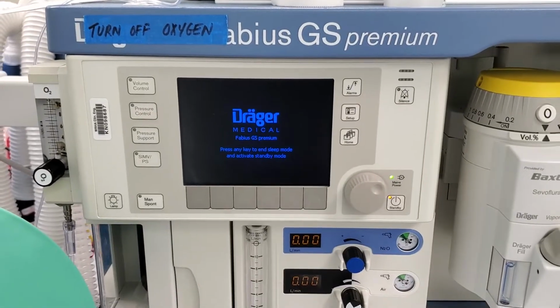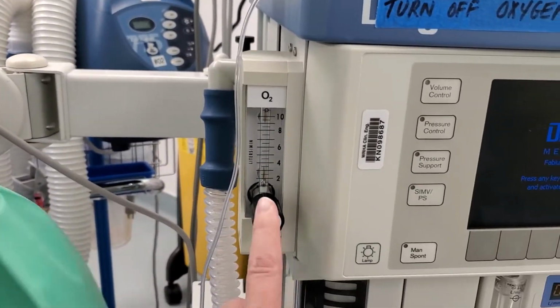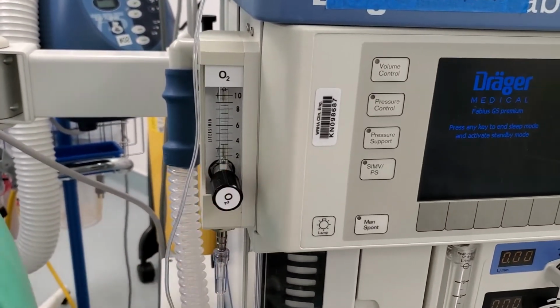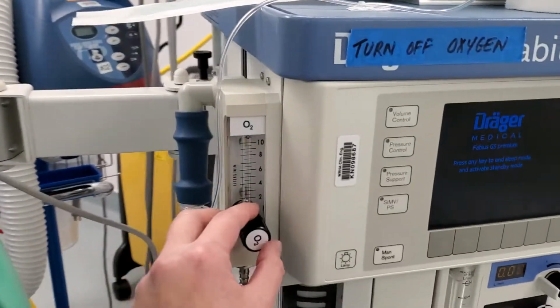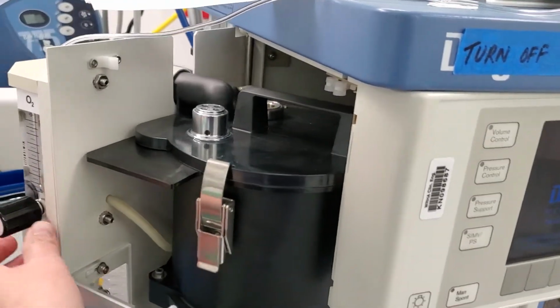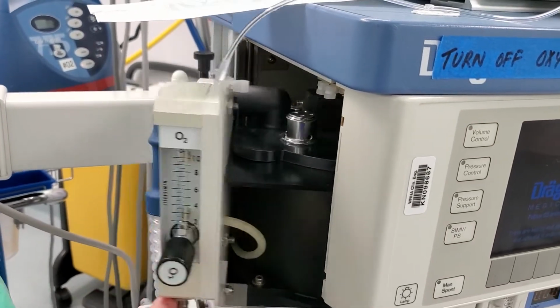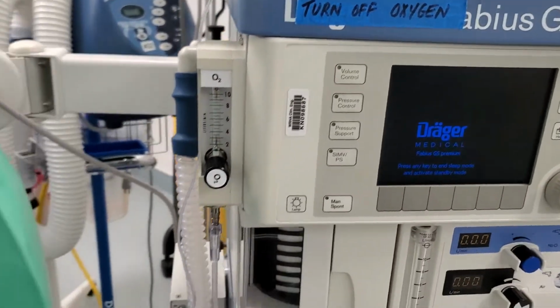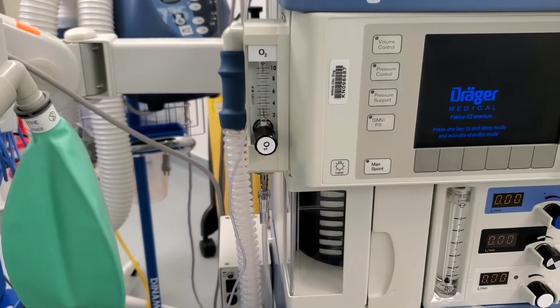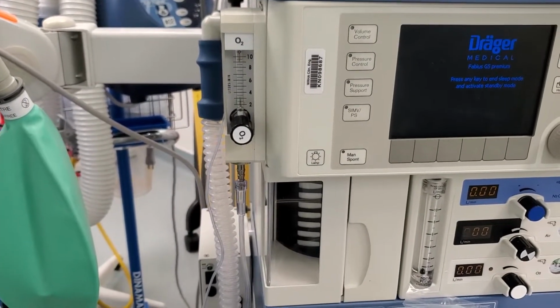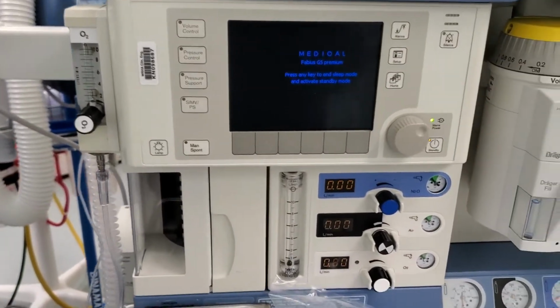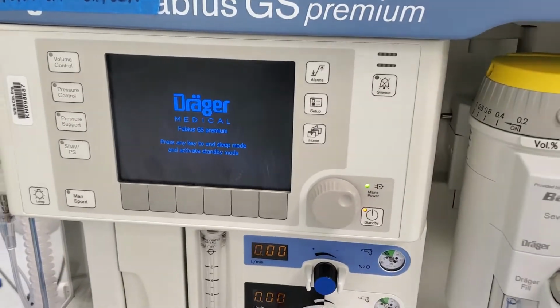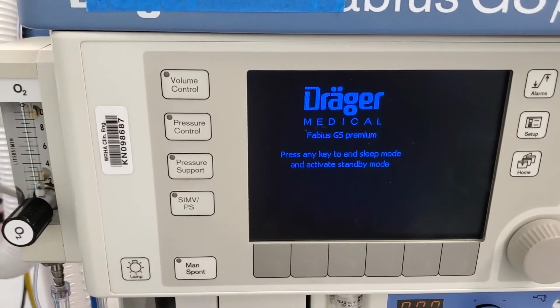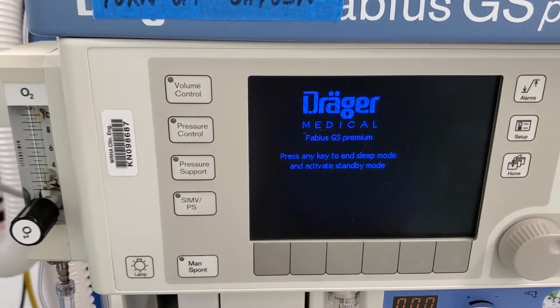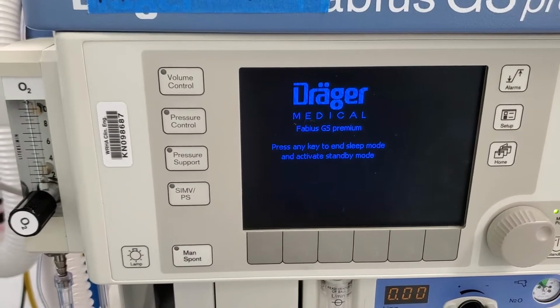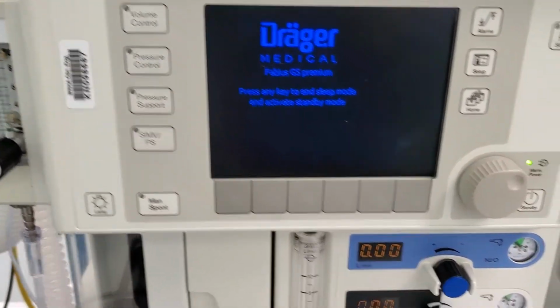The face of the machine here, we have an auxiliary flow meter. This is what we hook up our patient's nasal prongs to. This machine is driven by a piston, so that's the piston inside. If you look in the lecture notes, there's a couple of different methods of delivery. There's a piston and there's also bellows. The notes explain the difference between those. Anesthesia ventilators are quite straightforward. We have 4 different modes: volume control, pressure support, SIMV with pressure support, and then manual spontaneous.